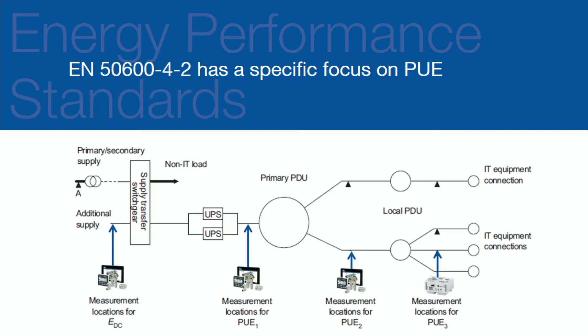The PUE, so Chapter 4 specifically mentions PUE, that was the performance part of the standard. Again, it specifies where you should be metering, and the more granular the metering, the higher the PUE number. So PUE 3 is where you're monitoring all the way through your infrastructure, right to the final load.